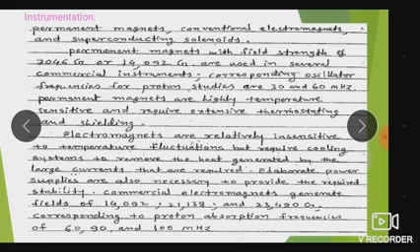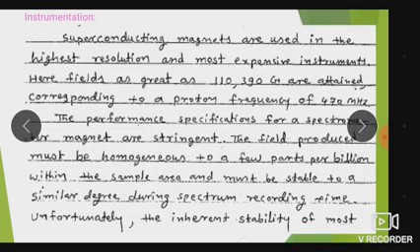Commercial electromagnets generate fields of about 14,092 gauss, 21,138 gauss, and 23,490 gauss. The corresponding proton absorption frequencies, that is RF frequencies, are 60, 90, and 100 megahertz: about 60 megahertz for 14,092 gauss, 90 megahertz for 21,138 gauss, and 100 megahertz for 23,490 gauss.